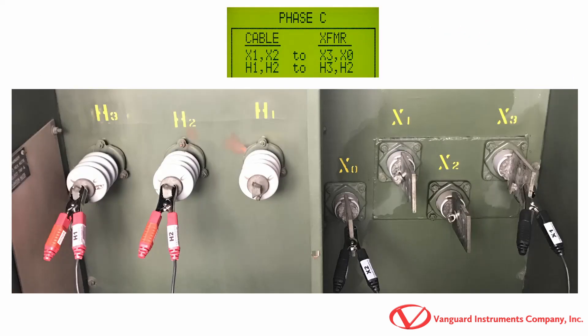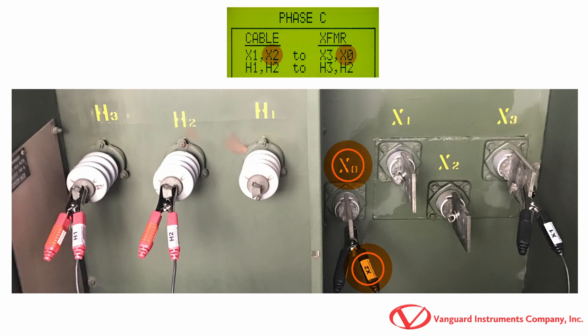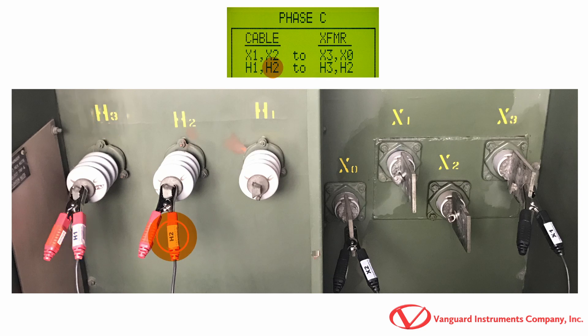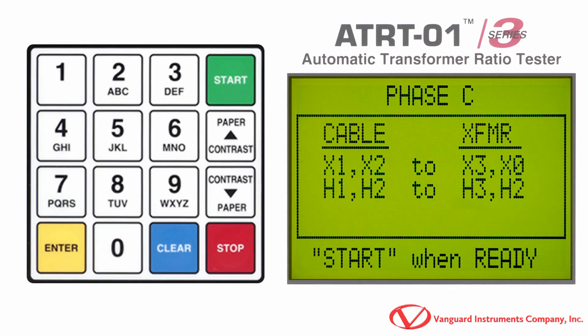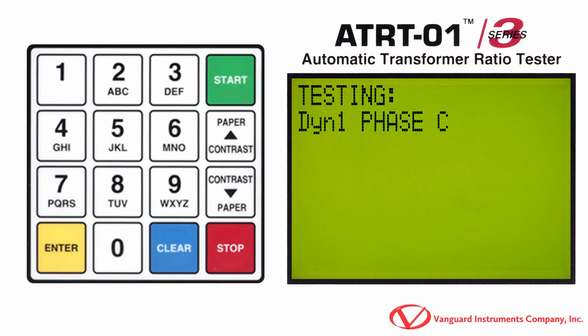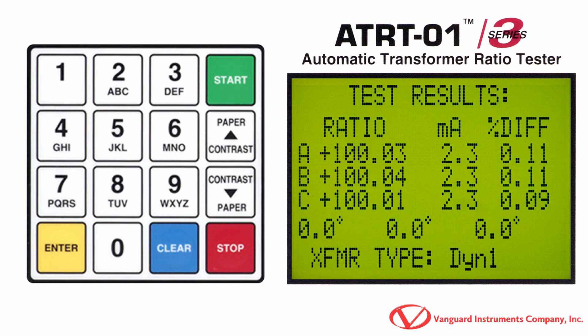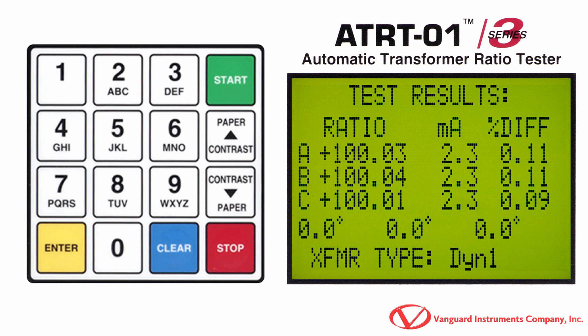Now we'll make the connections for testing phase C as shown on the screen. We'll connect the unit's X1 cable to the transformer's X3 terminal and the unit's X2 cable to the transformer's X0 terminal. Then we'll connect the unit's H1 cable to the transformer's H3 terminal and the unit's H2 cable to the transformer's H2 terminal. Press the Start key to run the test. After a few seconds, the test results for phase C will be displayed below the phase A and B results. Also, the phase angles for phase A, B, and C are displayed at the bottom of the test results from left to right respectively. 0 or 360 degrees indicates in-phase while 180 degrees indicates out-of-phase. Review your test results and then press any key to continue.